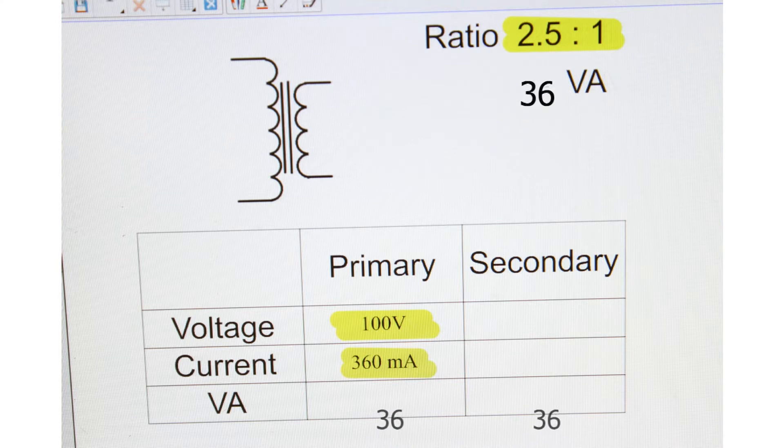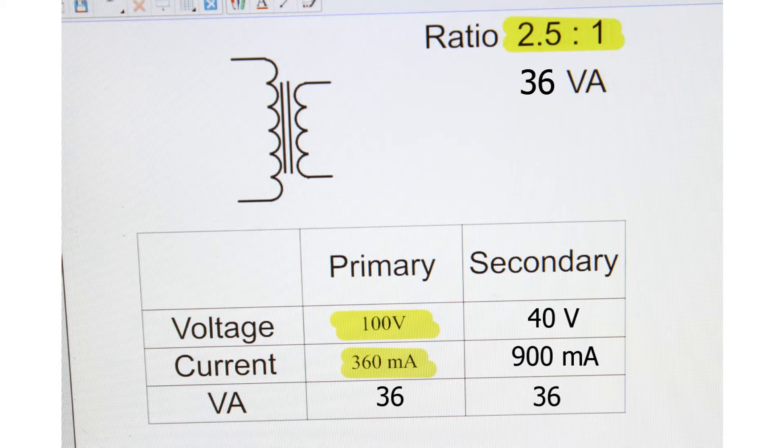Multiply 100 volts times 360 milliamps gives you 36 volt amps. Since it's a 2.5 to 1 ratio, we take the 100 divided by 2.5 and come up with 40. 40 goes into 36, 900 milliamps.